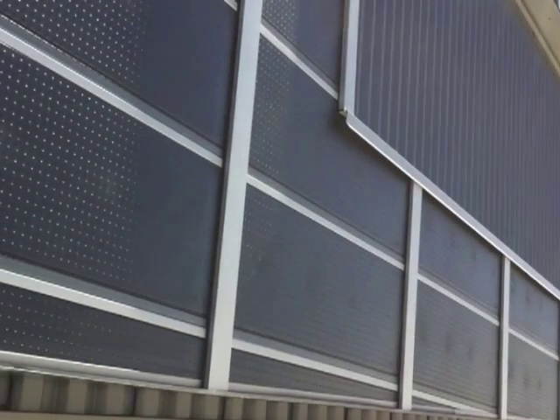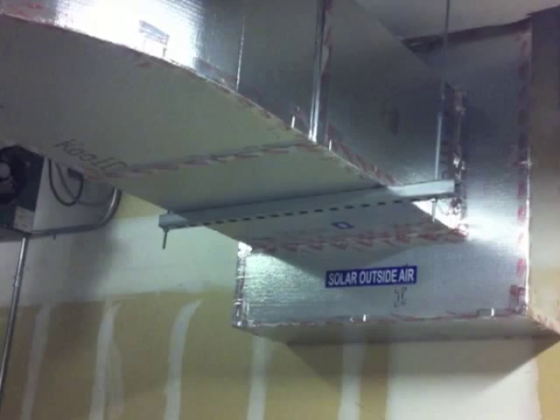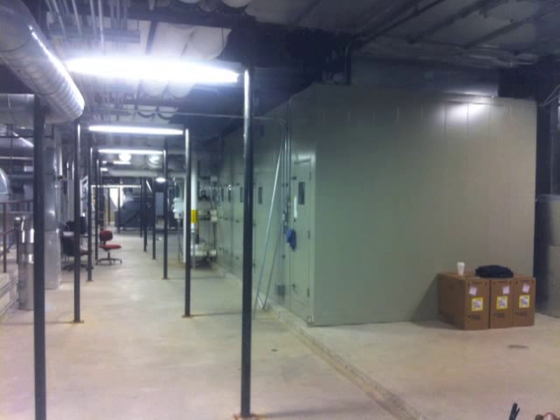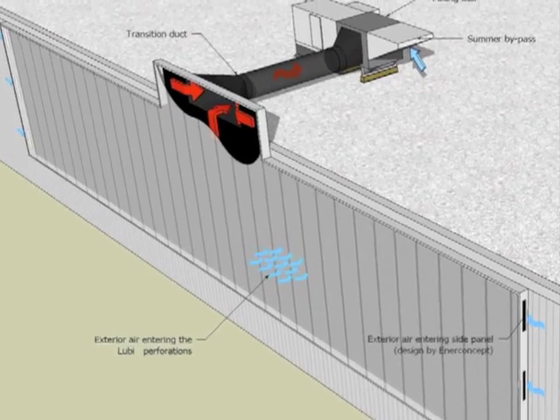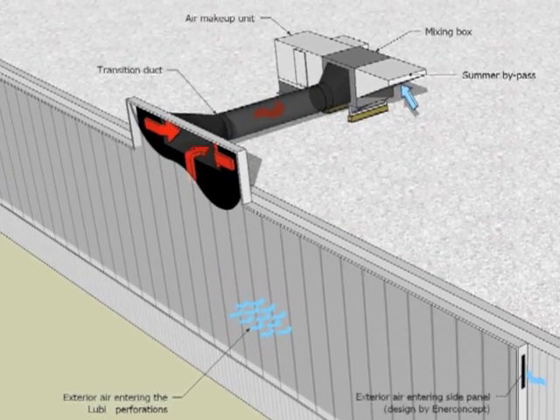With the Lubi glazing system in place, we now have the ability to absorb heat onto the wall, trap it, and introduce it into the building via ductwork. The ductwork is connected to the outside air intake plenum for the mechanical systems. There are two air handlers, and both now have ductwork connected to where they bring in fresh air. In the wintertime, the system draws its air through the solar air heating system first so that it can get preheated along the way.